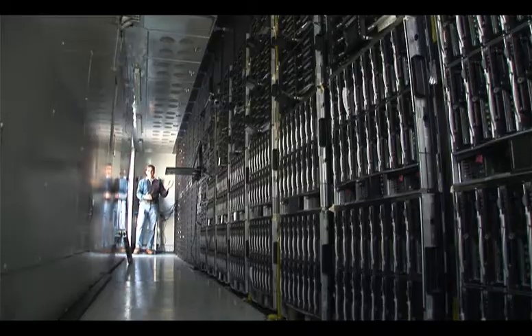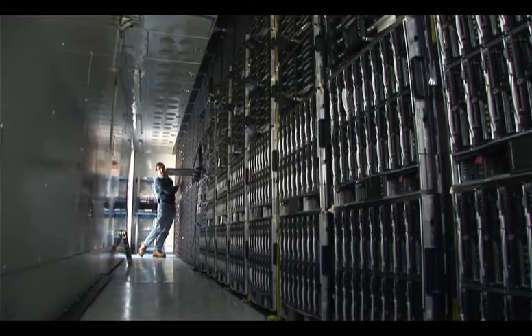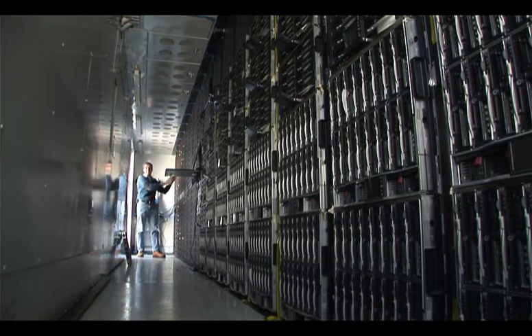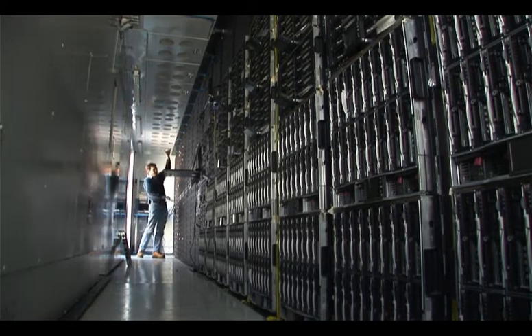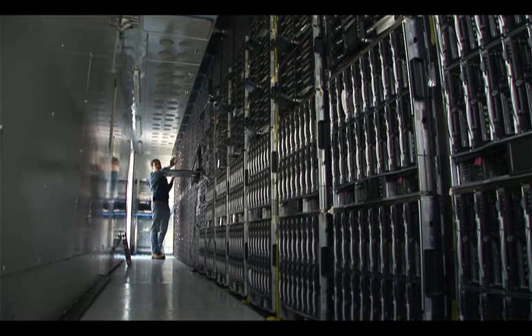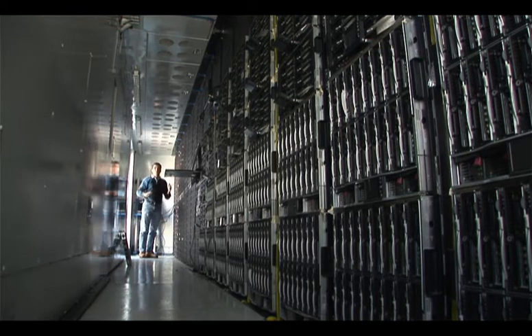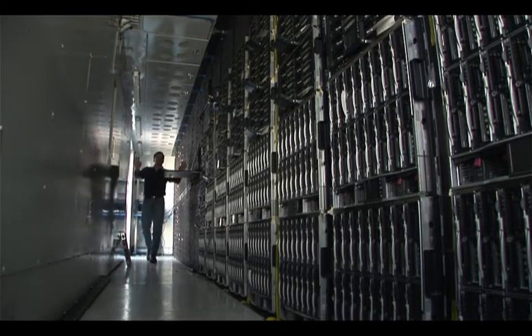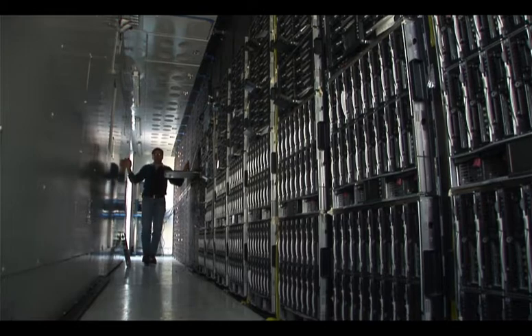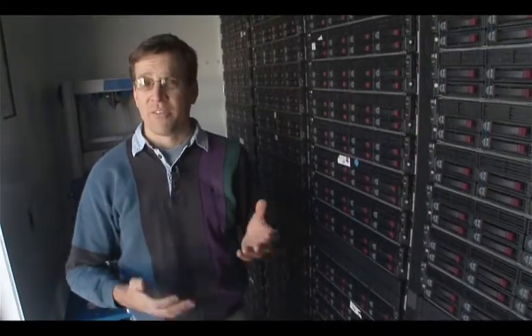We come inside and we see that anybody's front to back air cooled equipment in a 19 inch rack, we can fit 50 U tall, 22 racks for 1100 U. We have a nice big spacious over three foot cold aisle for servicing everybody's equipment.